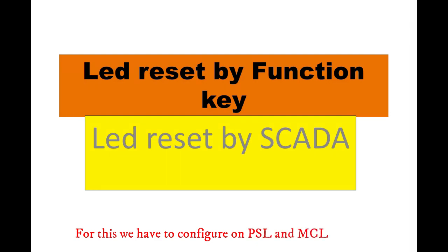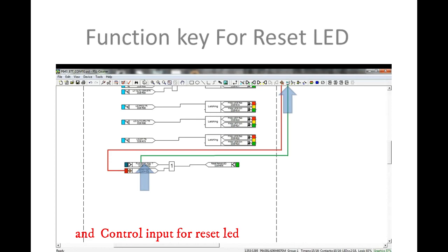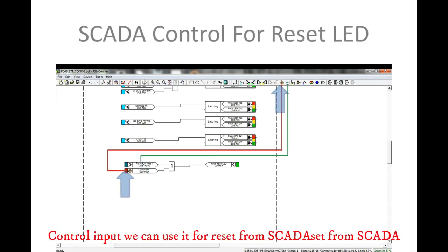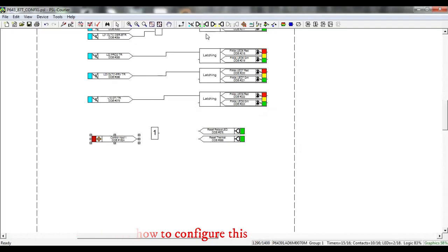For this, we have to configure on PSL and MCL. In PSL, first we have to configure for function key and control input for reset LED. Function key we can use for reset LED from relay, and control input we can use for reset from SCADA. We can see how to configure this from PSL.